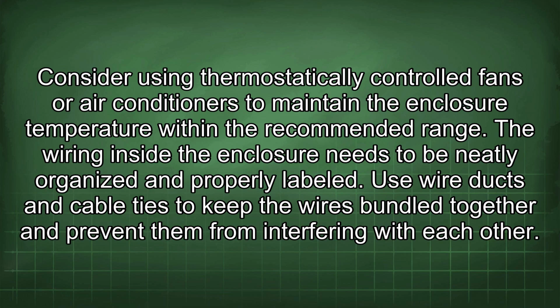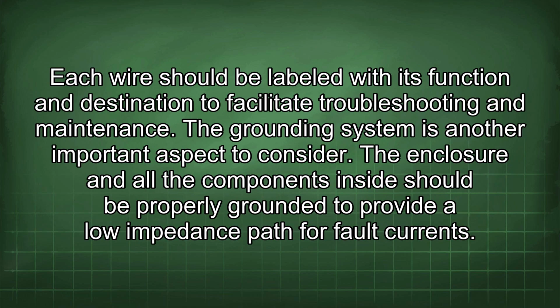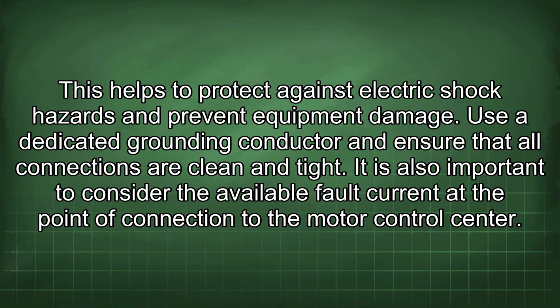The wiring inside the enclosure needs to be neatly organized and properly labeled. Use wire ducts and cable ties to keep the wires bundled together and prevent them from interfering with each other. Each wire should be labeled with its function and destination to facilitate troubleshooting and maintenance. The grounding system is another important aspect to consider. The enclosure and all the components inside should be properly grounded to provide a low impedance path for fault currents. This helps to protect against electric shock hazards and prevent equipment damage. Use a dedicated grounding conductor and ensure that all connections are clean and tight.